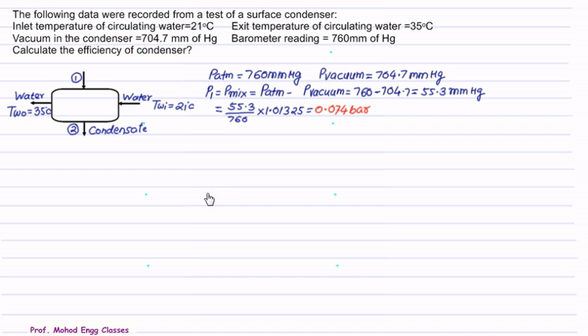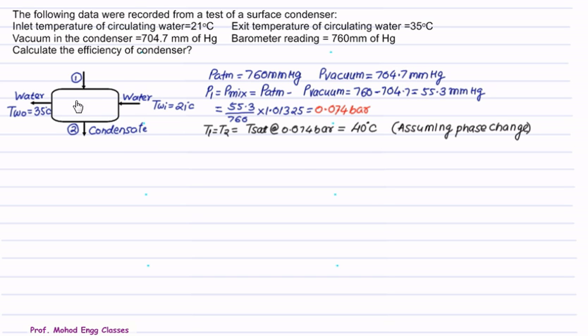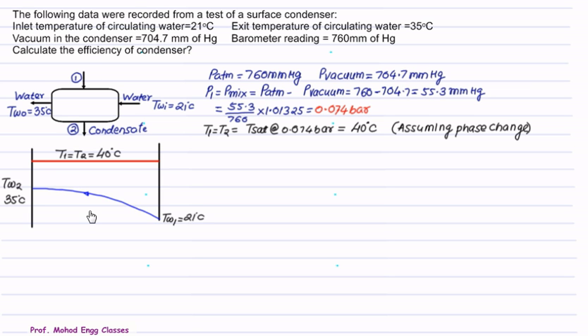Converting 55.3 mm of Hg to bar: 55.3/760 × 1.01325 ≈ 0.074 bar. Assuming only phase change occurs, the saturation temperature at approximately 0.07 bar from the steam table is about 40°C. So steam enters at 40°C and condensate leaves at 40°C. On a temperature plot, T1 = T2 = T_sat = 40°C.